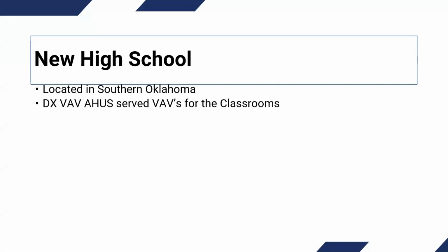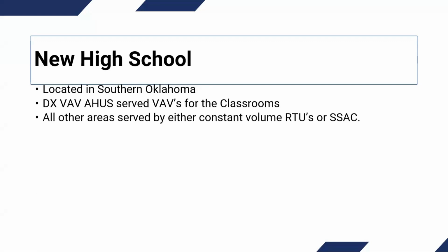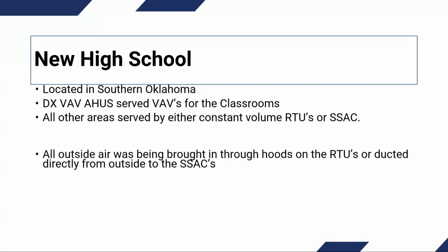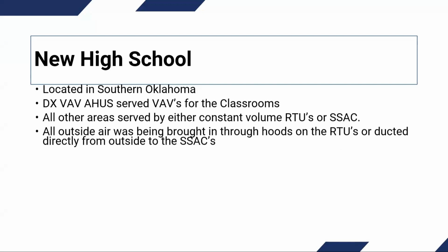So this particular school was all DX. It had DX central station air handlers with VAVs that served the classrooms. All other areas were either constant volume rooftop units or split system AC units. They did not have any dedicated outside air units on this particular project. All the outside air was being brought in through the hoods on the rooftop units, or it was ducted directly into the returns of the split system ACs.